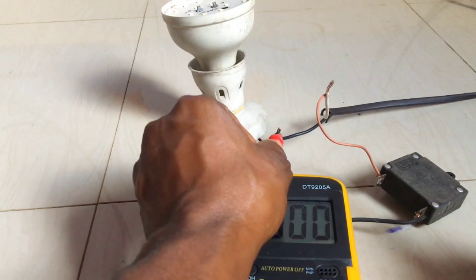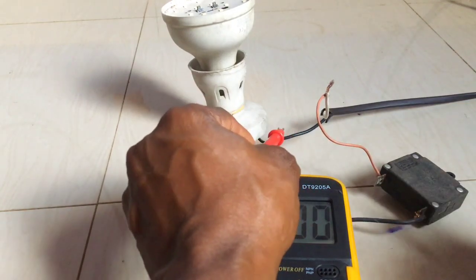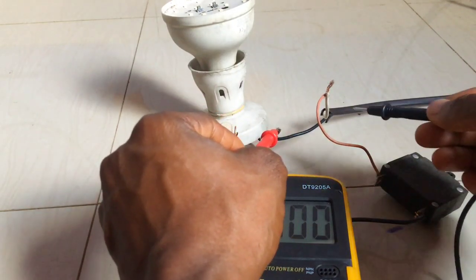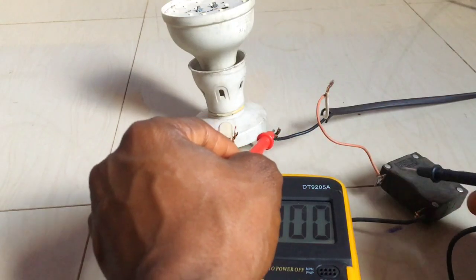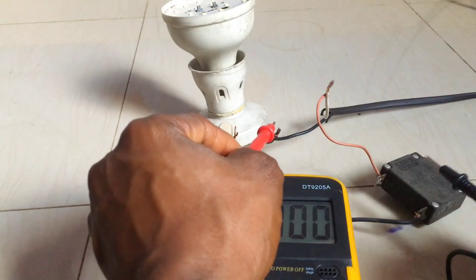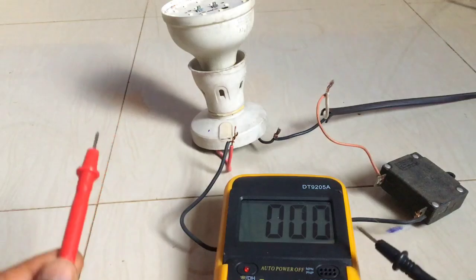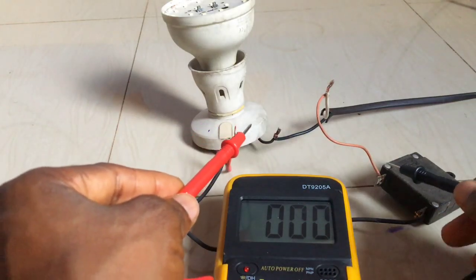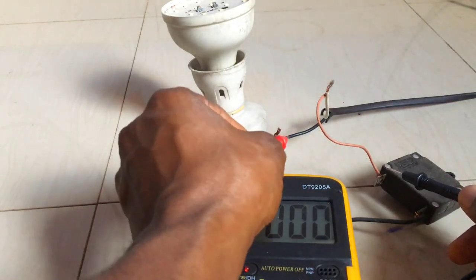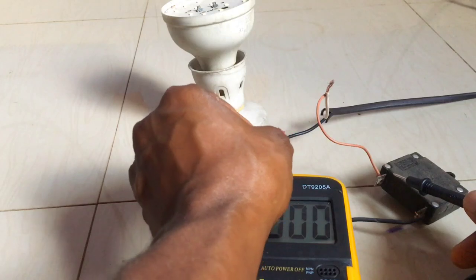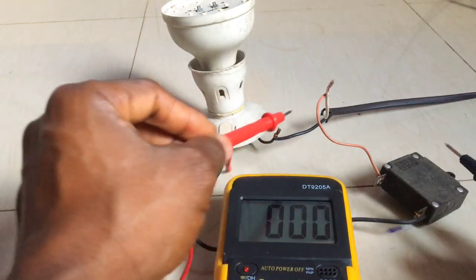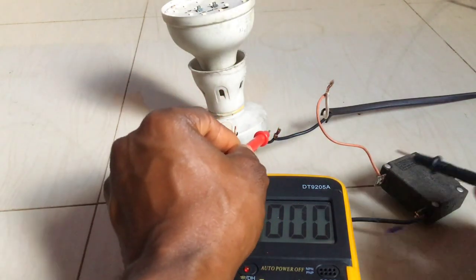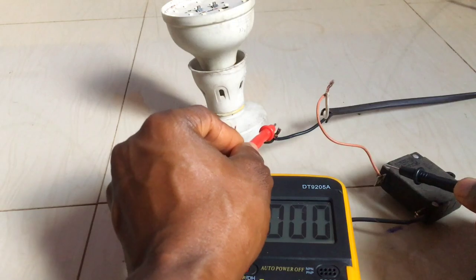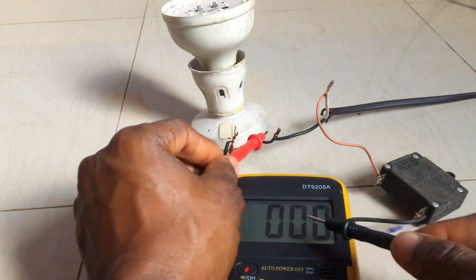All right, so this is our neutral link. Whether the switch is on or off, if the supply line, that's the red line supplying the switch at the common terminal, is energized, you should get a voltage reading across the common terminal and neutral. Remember, this is neutral, right? I don't know if you are seeing it. This is neutral and this is our common. So provided the common line is through and is energized, we should be getting a voltage reading.